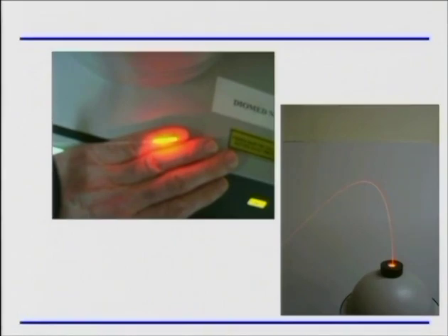Now, you have to do something like that to measure light from a diffuser. You have to have some way of collecting all the light. Otherwise, it's very difficult because light is coming out in all directions. So the idea of an integrating sphere is that the light bounces about inside this sphere. It's coated with a white, highly reflective coating. The light bounces about, and there's a little aperture in the corner which takes off a certain percentage of the light. Based on that percentage that comes off, you can then calculate the total amount of light that was delivered by the fiber. So I can now say I've given 1 watt, 2 watts, 3 watts, or whatever. And that's the reason that you use an integrating sphere to collect all the light from a diffuser.